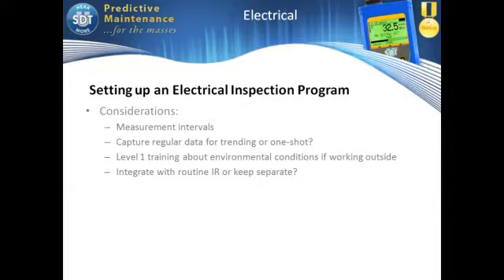Ultrasound gives you the opportunity of doing on-condition cleaning. There are guys combining ultrasound, infrared, and dry ice cleaning to go to a transformer that's running live and say that bushing needs cleaning, then using dry ice live to clean that one bushing, then going back to check and confirm it's okay now. So when we think about find it, fix it, check it, we've found a problem, dealt with it, proved it's gone away, and it's been completely non-intrusive.